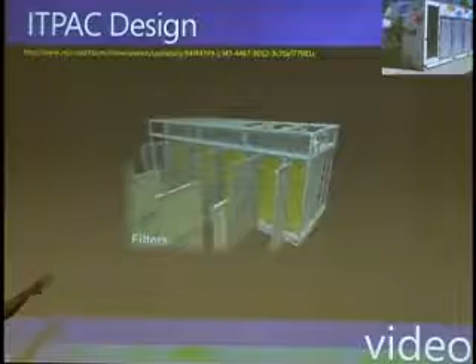So here's 4 modes of operation. Normal operation: air just comes in, hot air moves out the back. Now watch the temperature, top left, as it starts to rise. If it gets above about 90 degrees, that's when you turn the evap washers on, so water runs down those, and now outside temperature is 104, but the inlet into the servers is only about 90. At night, if it cools off, you can go back into normal operating mode.